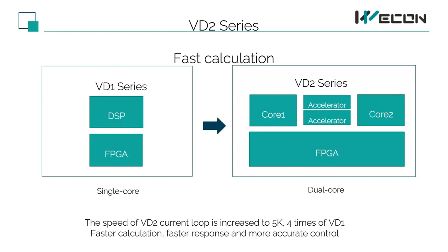There are high-speed current loops, PIDs, and various filtering algorithms in Wecon servo — these are the strengths of DSP CPUs. Therefore, the VD2 series of servo drives not only still use the DSP CPU solution, but also use dual DSP CPU, plus two additional accelerators, as well as FPGA as an auxiliary. Through calculation, the VD2 current loop speed is increased to 5K, which is 4 times that of VD1, making VD2 calculate faster, respond faster, and control with more accuracy.